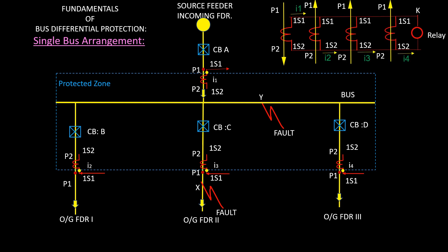The locations of the current transformers (CTs) define the boundary of a differential protection zone. In differential protection, CTs are oriented so that a line drawn from the polarity mark to the protected equipment passes through the CT. The opposite polarity convention can also be used if it is applied to all CTs in the differential zone. The figure here shows four CTs that form a bus differential protection zone. If a bus fault is detected within this zone, all terminal circuit breakers within the differential zone will trip.